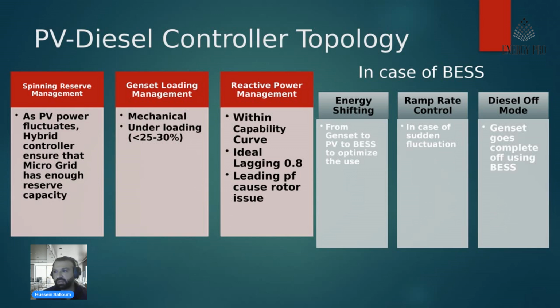And the third part is that it controls the reactive power management. As all generators have an ideal performance between 0.8 and 1 lagging. So in case it's below 0.8, it will start to lose. If it's above 1, it will start to act as a rotor, and also we will have losses. So the powerhouse controller will always try to control the power factor to be between 0.8 and 1. So these 3 philosophies are in control for the powerhouse management between the PV and the diesel generator. Now, in case we have an energy storage system, another 3 control philosophies come into place.